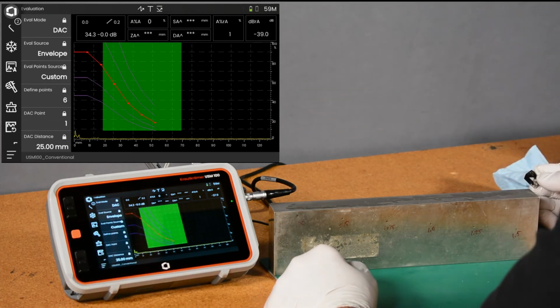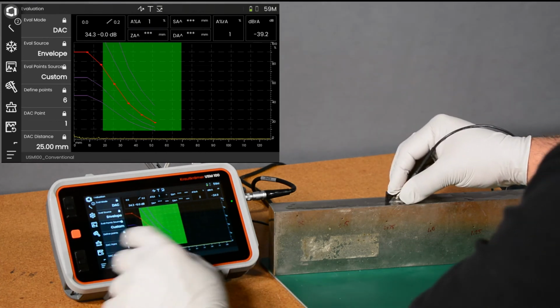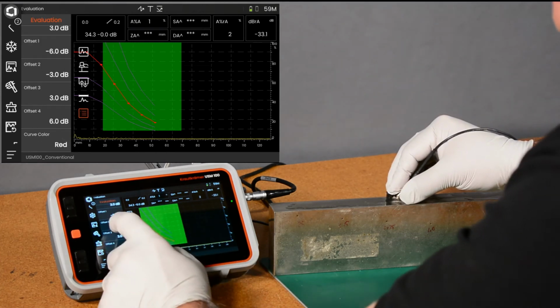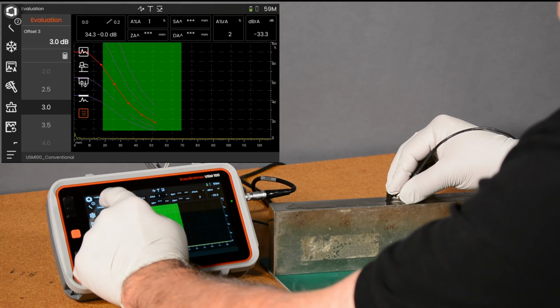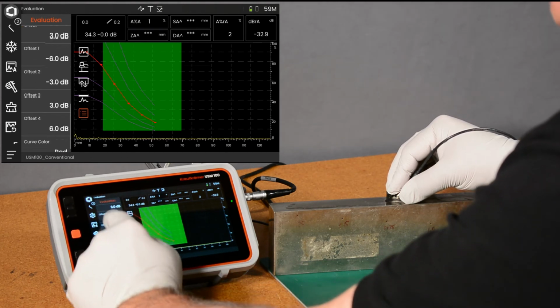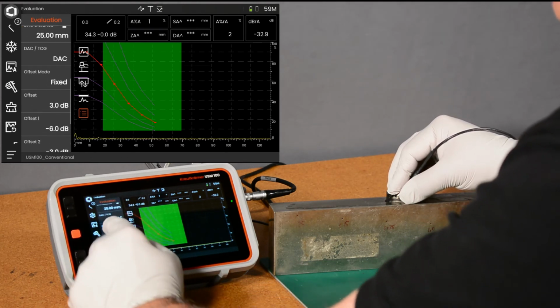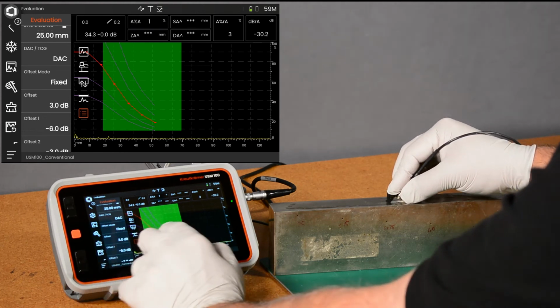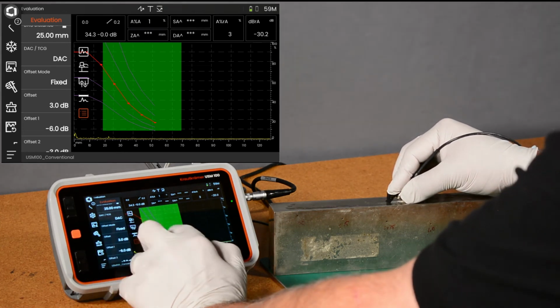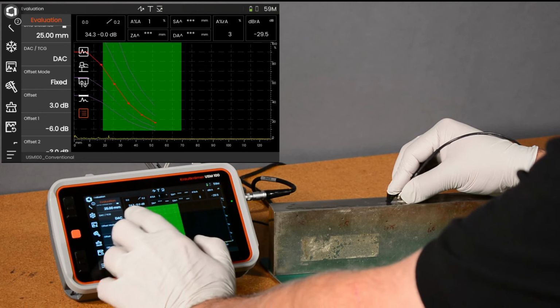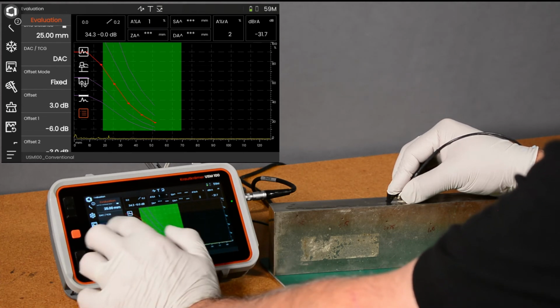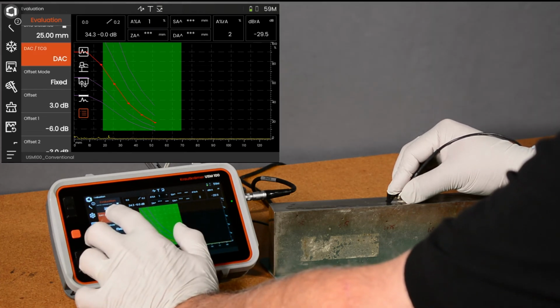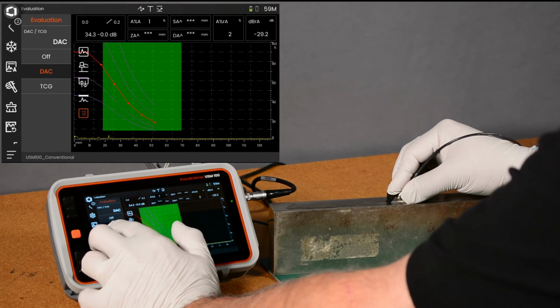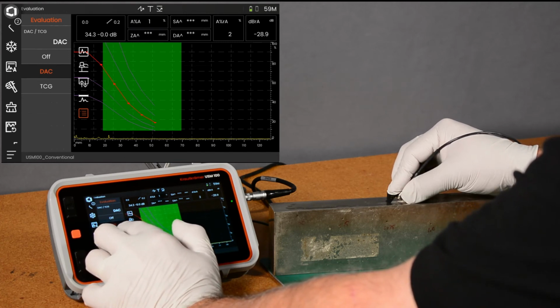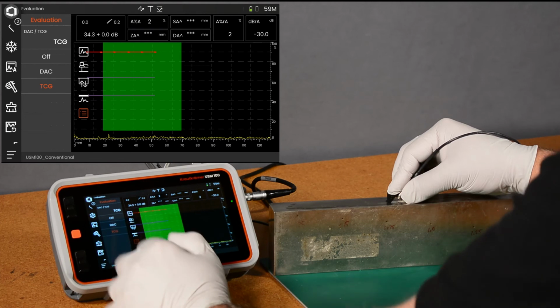That's the essentials of setting up a DAC curve. If we go to our evaluation menu and we look here, scroll up a little bit. I have the choice of either displaying things as a DAC curve, where you have an amplitude curve recorded and displayed on the screen, or we can switch from DAC to TCG mode. So from distance amplitude correction, we're going to switch to time corrected gain mode.